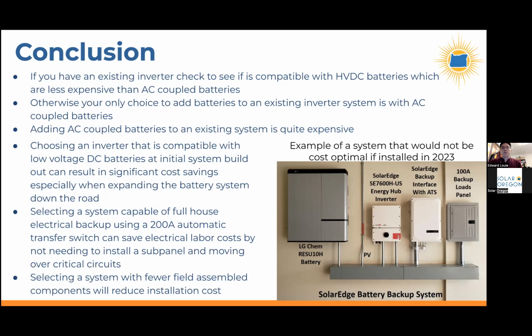Whatever system you choose, look into the cost of a 200 amp automatic transfer switch, because transferring your main circuit breaker to full house backup can be less expensive than the electrical labor cost to install a sub panel and move circuits over to it. We think the 200 amp automatic transfer switch costs around $1,800. You could easily exceed that in labor and material costs to add a sub panel. So even though it sounds expensive, it's actually not.